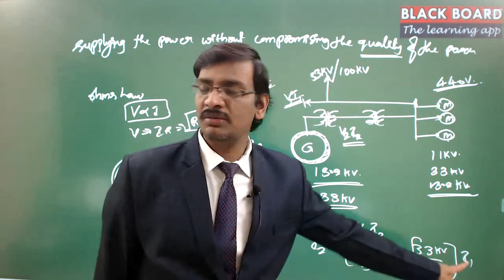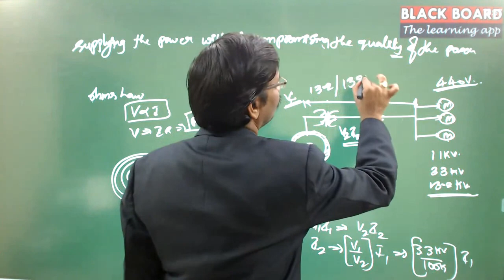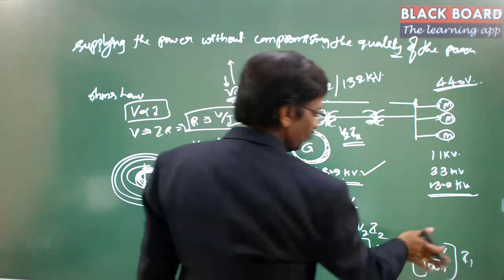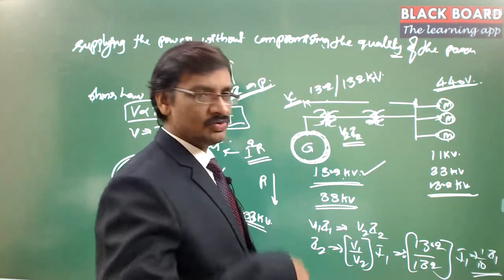That means if we raise the voltage, let's take a simpler calculation: suppose 13.2 kV is the generated power, stepped up via 13.2 kV divided by 132 kV. If you give this to the transformer, the voltage is raised 10 times and the current will be reduced by 10 times. So this becomes 1 by 10. That is, 13.2 divided by 132 into I1, which is 1 by 10 times of I1. So the current is reduced by 1 by 10.